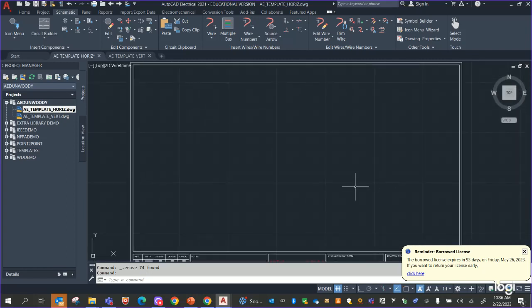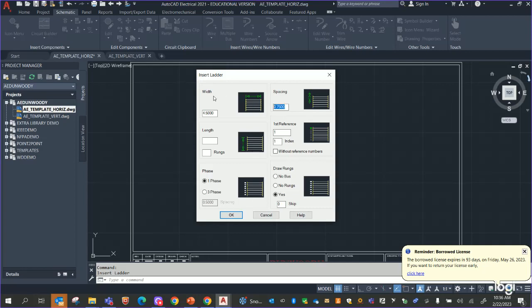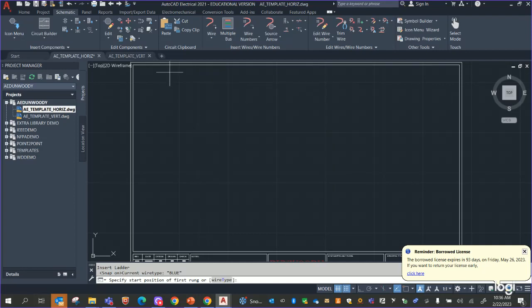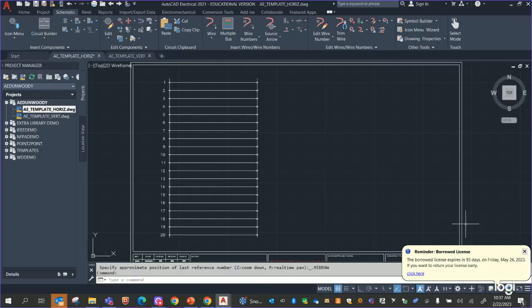What we'll do is start off by creating a simple ladder diagram. We'll consider this a PLC input module that somebody's going to be wiring up out in the field. We'll add a ladder and insert it into our diagram. I'm going to create the spacing at 0.4 — I could always change this later. A 0.4 spacing for this particular template works out pretty well. I'll go ahead and hit 0.4, make sure I'm on single phase so I get a nice clean ladder, then drag my ladder down. It's going to connect all the rungs together, which is fine because when we insert the parametric PLC input module, it's going to insert itself and take care of all the wiring for us.